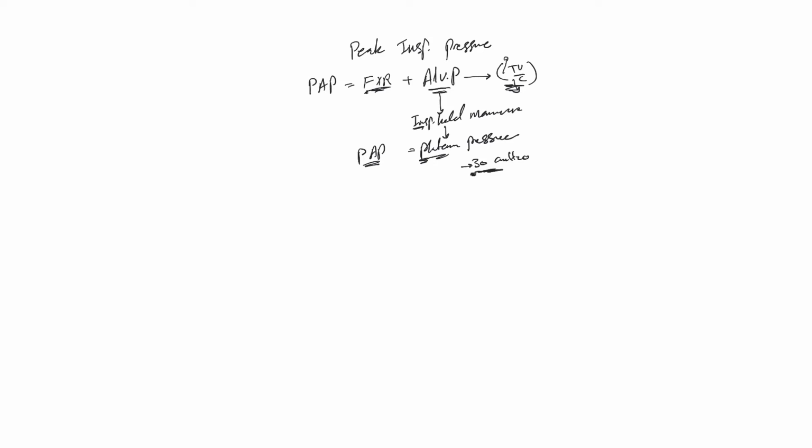If there's a problem with very large tidal volume, you need to cut down. Very high flow rate, you need to cut down on that, because flow rate, you have to remember, is very related to tidal volume from my previous video as well. Now if the problem is not here, then the problem is here or here. If there is very high flow rate, that will lead to very high tidal volume, as we said. So you just simply decrease flow rate.